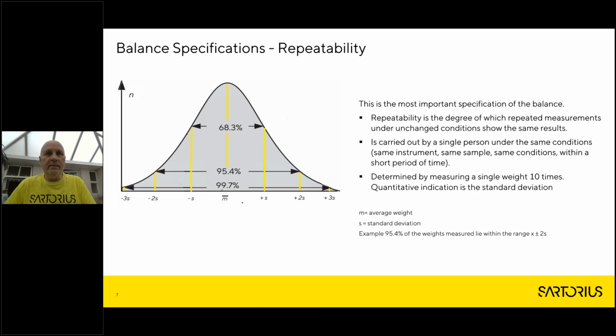Our first specification here is repeatability of the balance. Repeatability is the most important specification on the balance. In effect, it tells us how good the balance is at giving the correct data time after time. We do a repeatability test by placing a weight, usually around 5% of the maximum capacity of the balance, 10 times, and calculating the standard deviation of those 10 weighing replications.